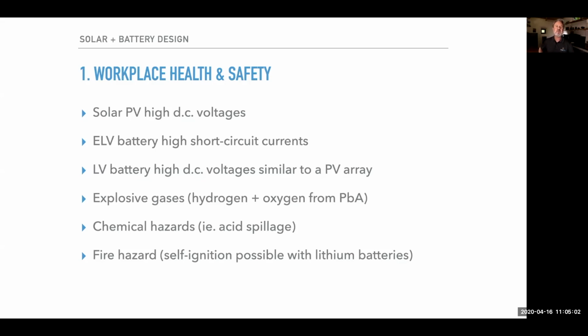So your typical grid tie systems, single phase, will be up around the sort of 400 or 500 volts DC. DC is inherently less safe than AC at similar voltage levels because of the propensity to cause internal burns. So you have to be very careful with DC. In fact, that's why there's licensing requirements. If you're working on systems over 120 volts DC, or 50 volts AC, you need to be a licensed electrician in New Zealand or Australia. And that's for good reason.